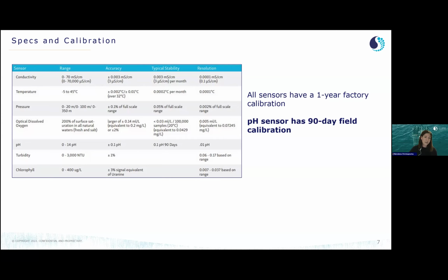All sensors in the HydroCAT-EP V2, except for the pH sensor, have a 1-year factory calibration. Seabird in general recommends a yearly calibration of all CTDs in our facilities to maintain their high performance and accuracy. The pH sensor is a glass electrode pH sensor and requires a 90-day field calibration. You can basically have multiple of these sensors, calibrate them in the lab, and then go and replace them in the field. The accuracy of the pH sensor is 0.1 pH and it can retain its stability for 90 days. So keep in mind that, in general, the main limiting factor of deployment time is the pH sensor here.